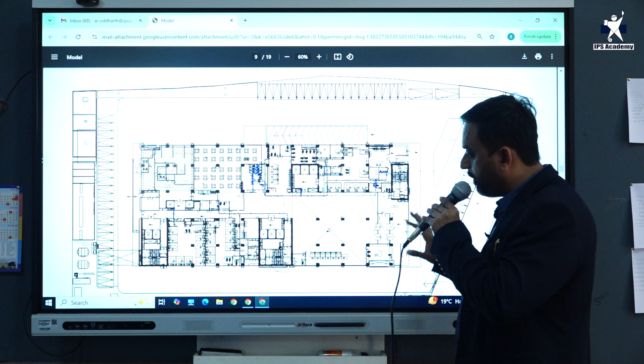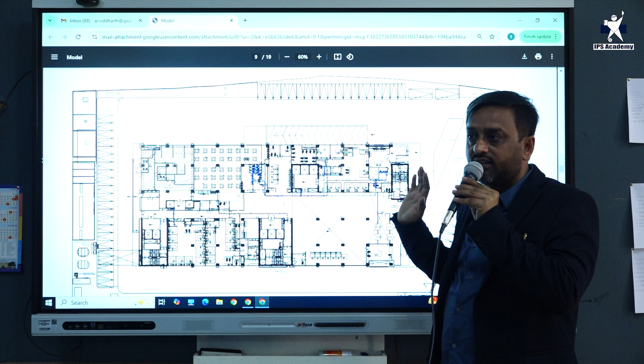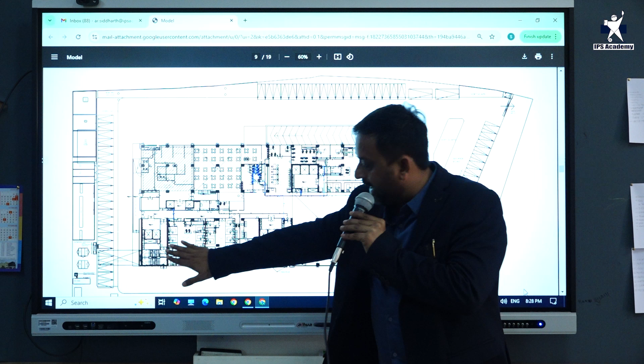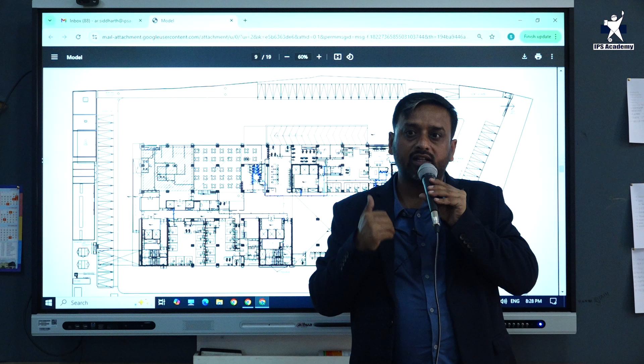If you are putting the staircases at the edges or corners, your staircase pressurization or ventilation gets eliminated. You can have natural ventilation also if all the staircases are next to the facade. Out of 3 staircases in the building, you need at least 1 fire staircase which can be used for egress. Because during a fire, you have to use the staircase only to egress to the ground directly.